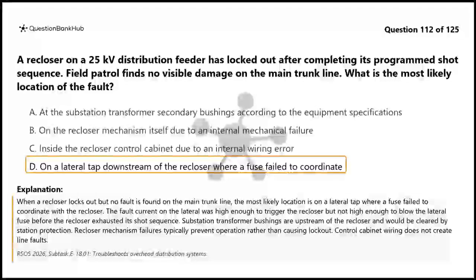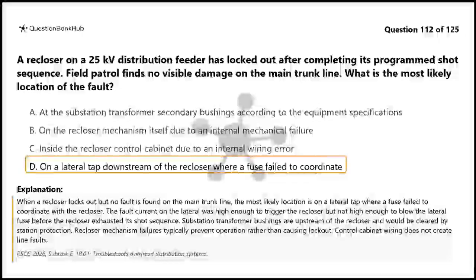Substation transformer bushings are upstream of the recloser and would be cleared by station protection. Recloser mechanism failures typically prevent operation rather than causing lockout. Control cabinet wiring does not create line faults.